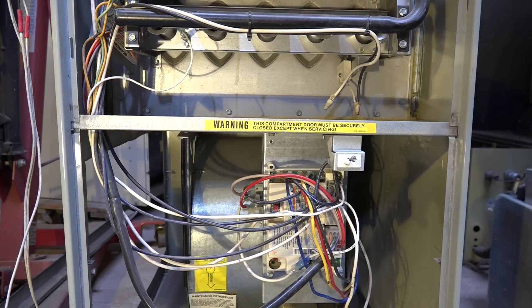Now we're going to go a little bit farther with this one and we're going to say the pressure switch was open but it didn't close. And let's see what the reaction of this thing is if for some reason the pressure switch did not close.